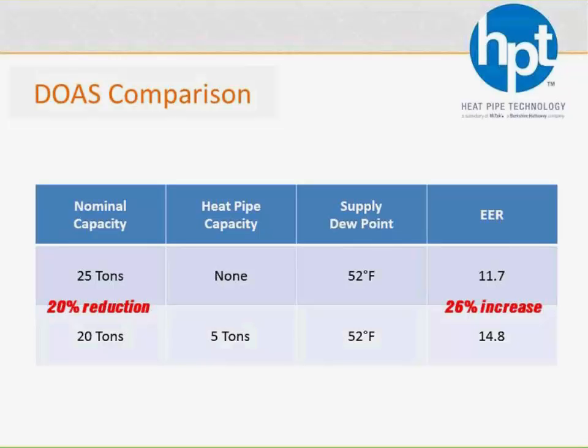So basically a heat pipe, no moving parts, requires a little bit more fan energy. So that brake horsepower is going to bump up just a hair, while the 25-ton system needs 5 tons of compressor power, and that takes a lot more power draw. So to get the same capacity, we're going to get ours a lot more efficiently. And the other bonus here is it may not cost you anything. To go down from 25 tons to 20 tons, yes, the heat pipe costs money, but you save money right off the bat by downsizing your system.